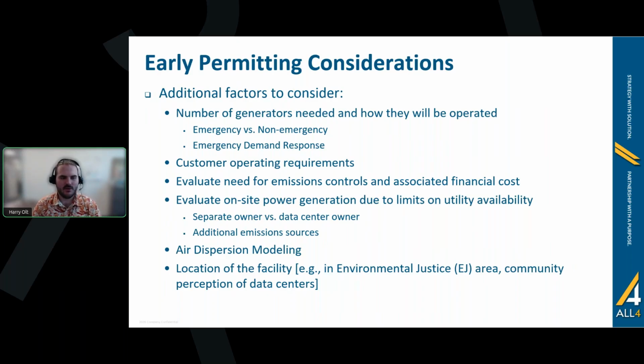Consider as early as possible if the permitting program requires air dispersion modeling. Not only can it result in a potentially longer review time prior to permit issuance, but the results could impact emissions controls, stack heights, and other parameters that are handy to know in the design phase.